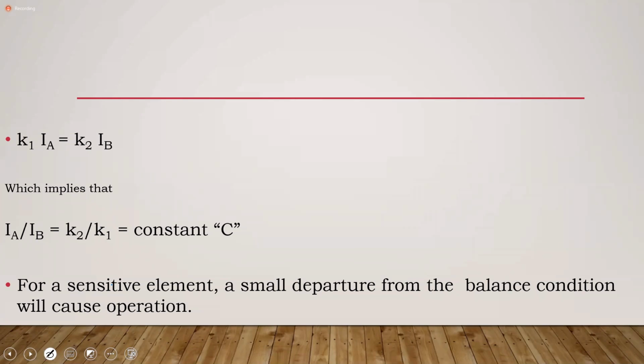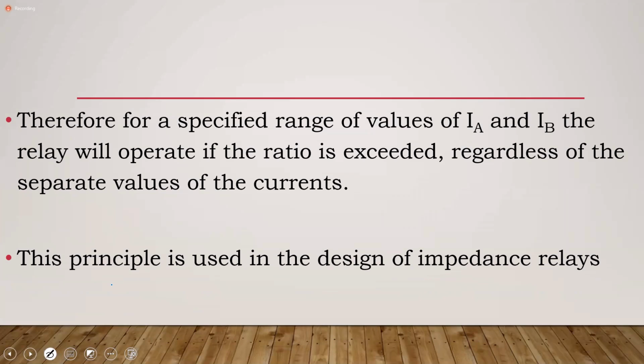So within a certain range of values, what we are saying is that the ratio, and this is important, is the ratio that, when exceeded, will cause operation. It isn't the actual values, it's the ratio. So A over B is a constant. If that ratio is violated, within a certain range, then operate. That's what the relay would be set up to do. And we use it for impedance relays.